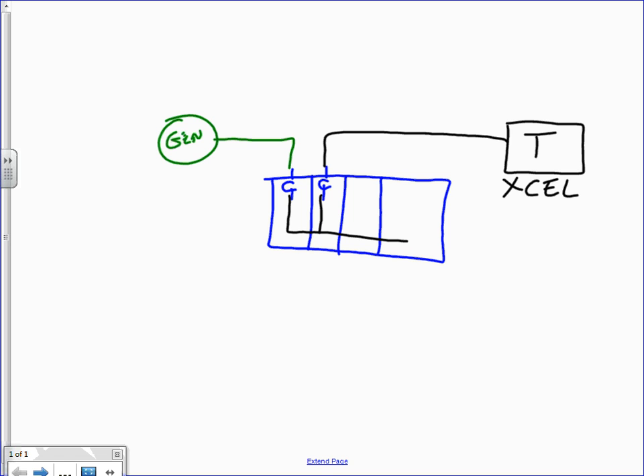Normally, of course, I'm being fed from my transformer from Xcel. If power fails, I'm dead. Paralleling gear senses that power has failed. It'll fire up the genset. It trips this breaker open, so I don't backfeed, and when the power comes in, it closes this breaker and come back. So that's how it works in loss of power in kind of an emergency mode.